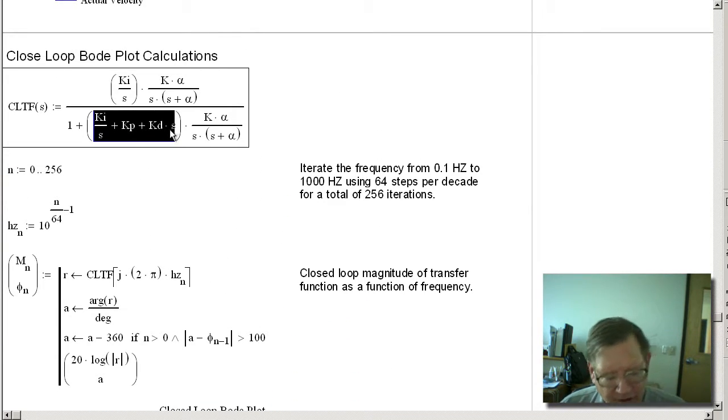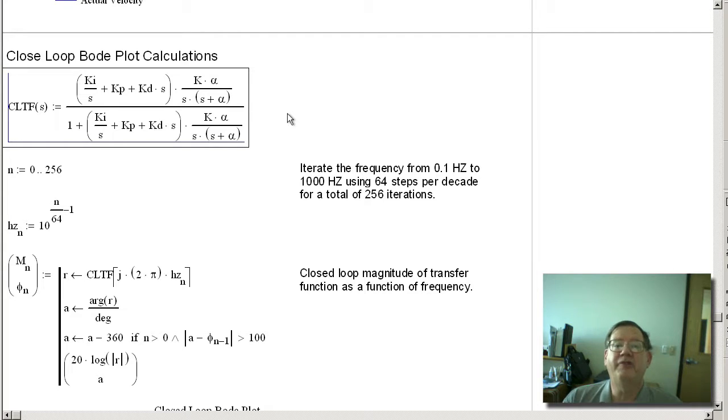So there's different options that you have with a PID. You can have all three gains be in the forward path. In other words, they're acting on the error. If you remove Kd from the forward path, that means that the derivative gain is only acting on the changes in position, or what people call the process variable. And if you remove Kp and Kd from the forward path, then the Kp and Kd are only acting on changes in the process variable or the position, and only the integrator is working on the error. I call this mode where the Kp and Kd are removed from the forward path, I-PD, and it has some uses in motion control.